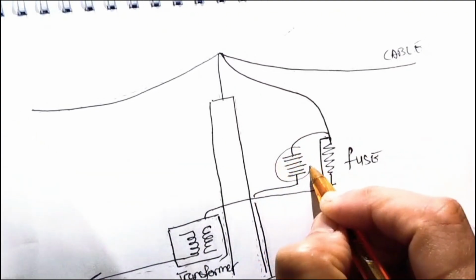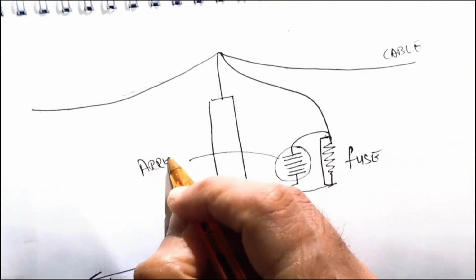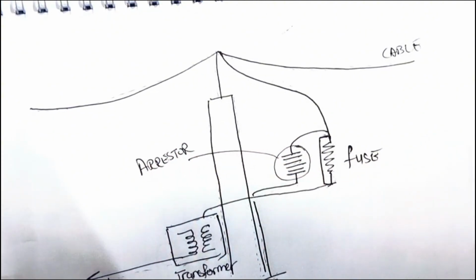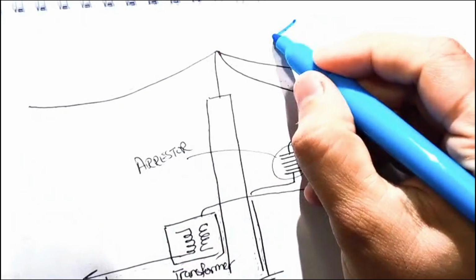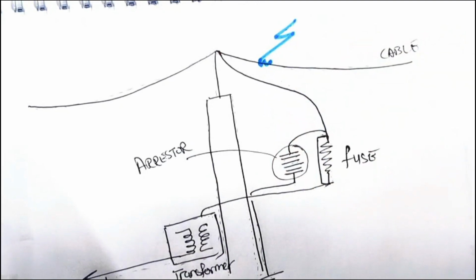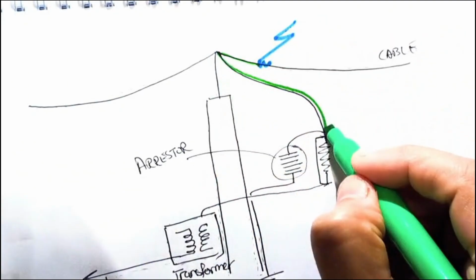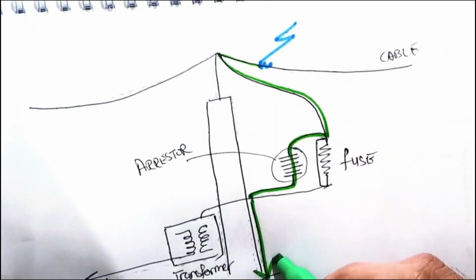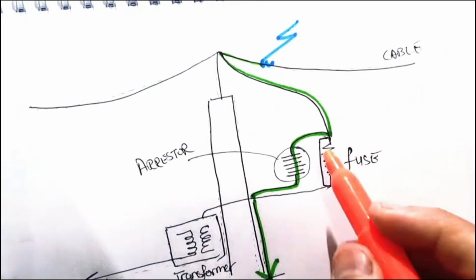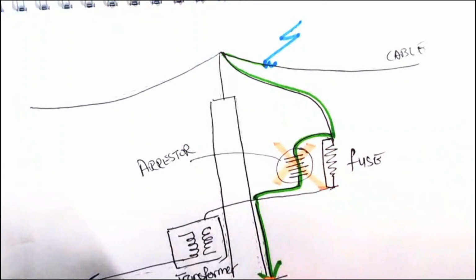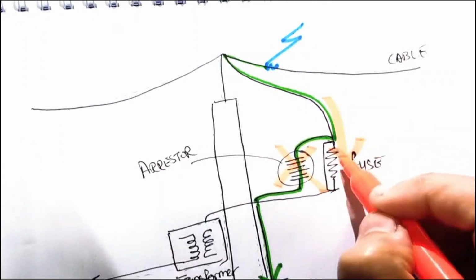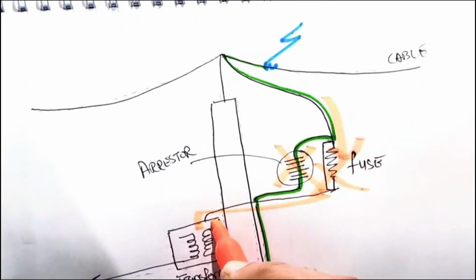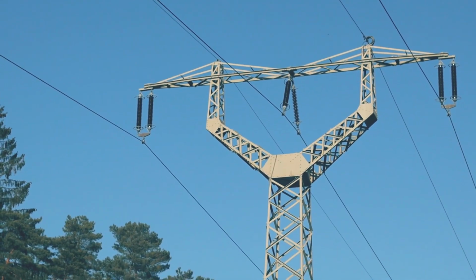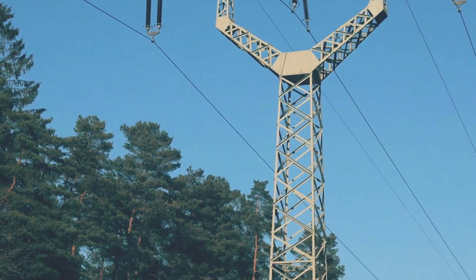So what's a lightning arrestor anyway? Think of it like a surge bodyguard for the grid. It's designed to catch high voltage spikes, usually from lightning, and simply dump that energy into the ground before it can fry your transformers or line. But if that arrestor fails, like it did in this case, the surge can go wild, trip protection systems, knock out the entire transmission line, or could even blow up the transformer. Basically, it's one tiny part with a huge responsibility.